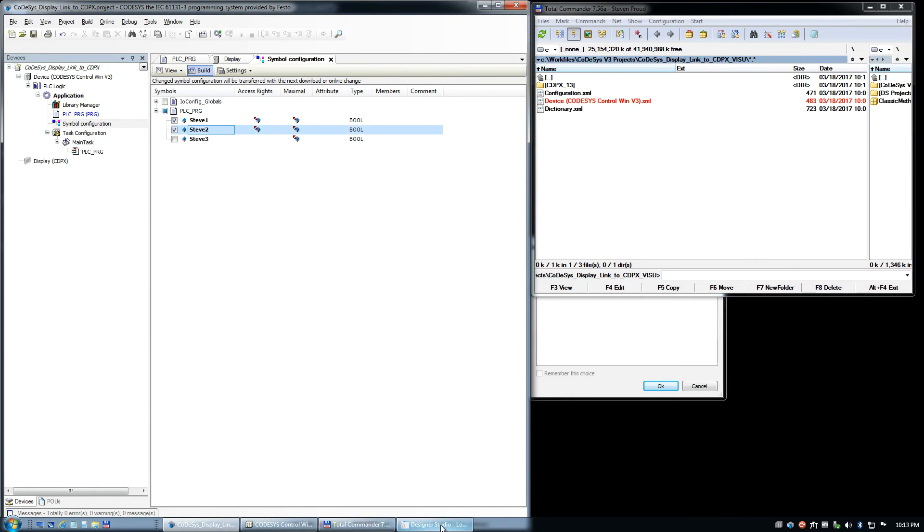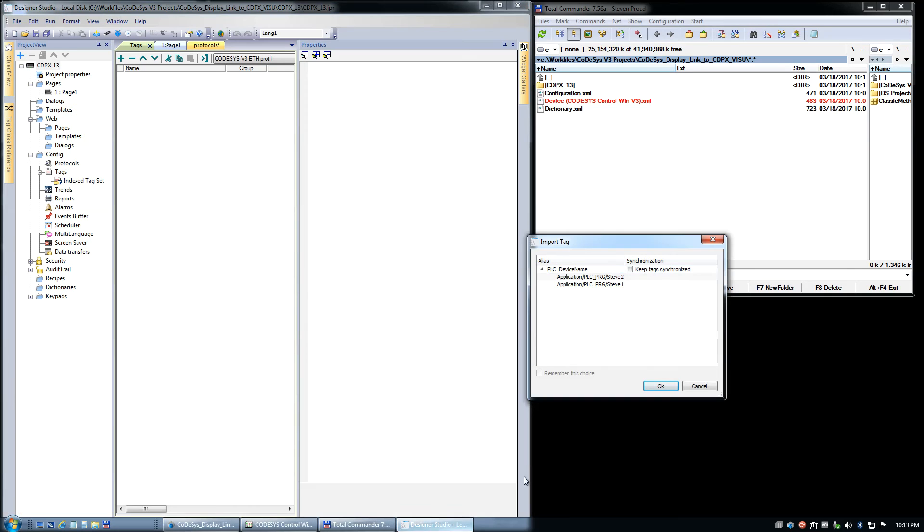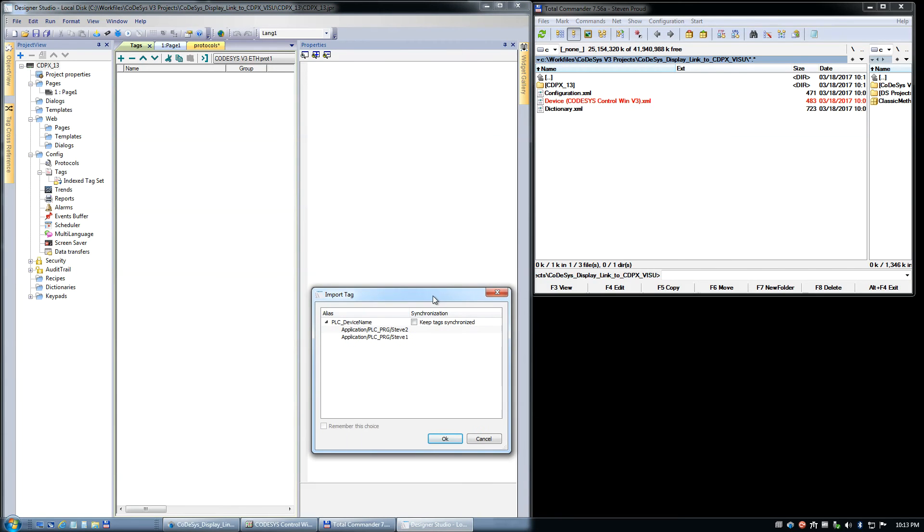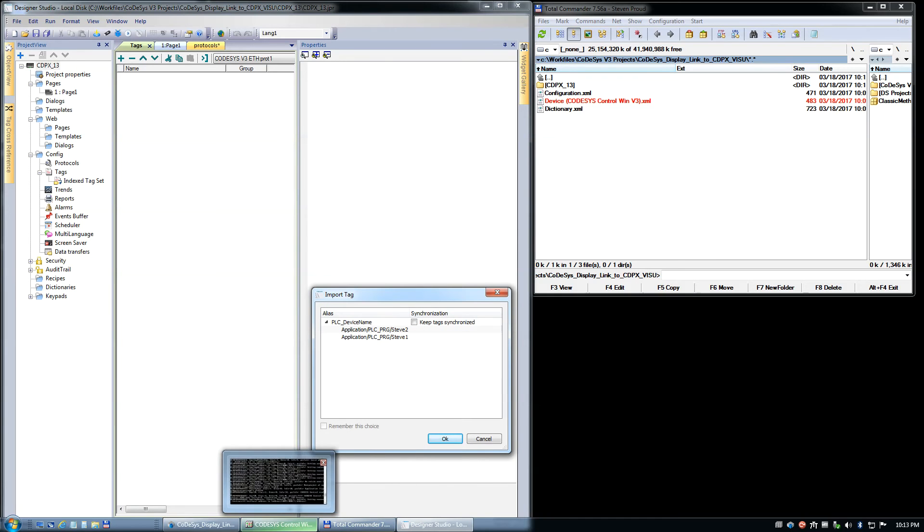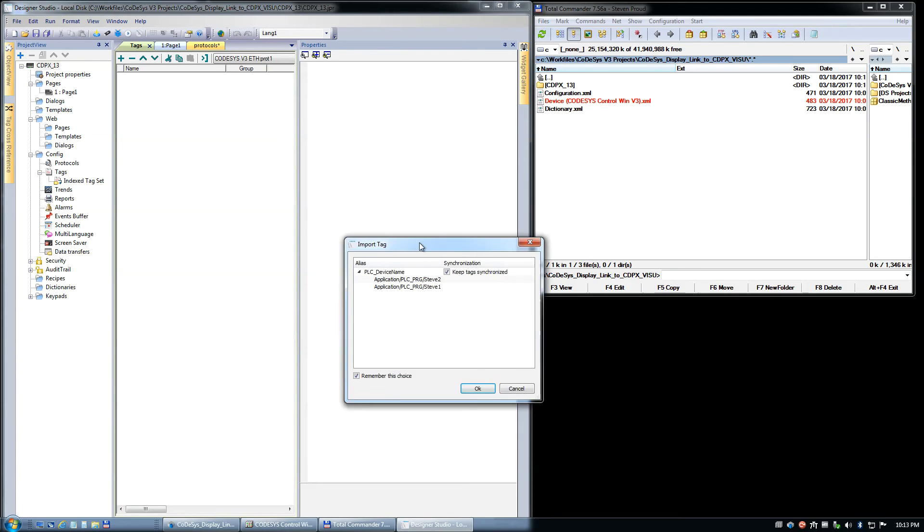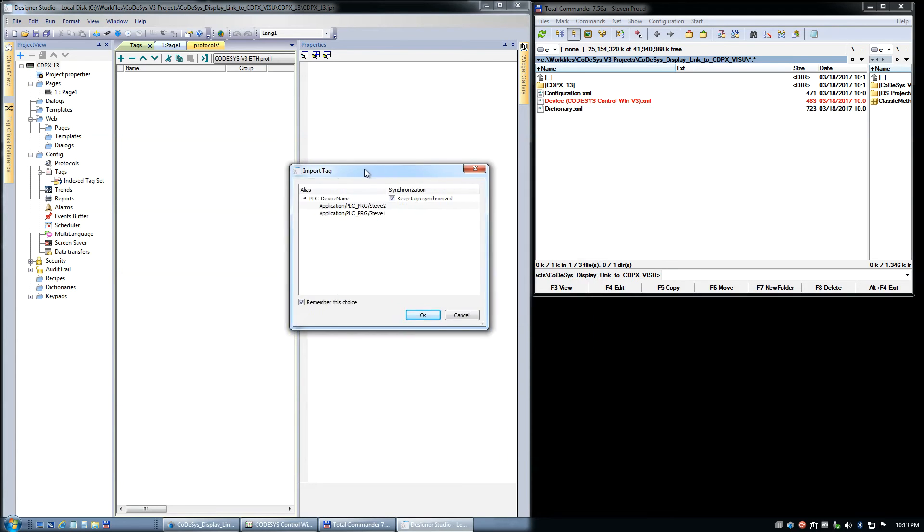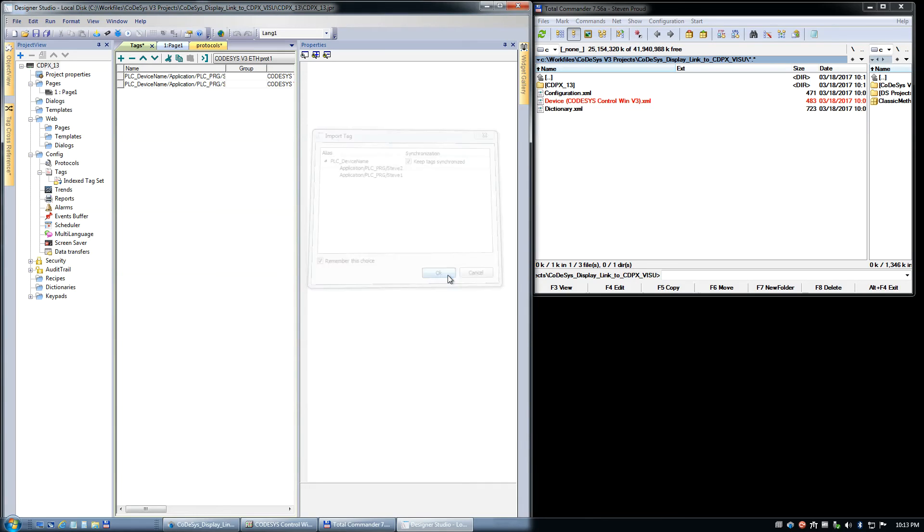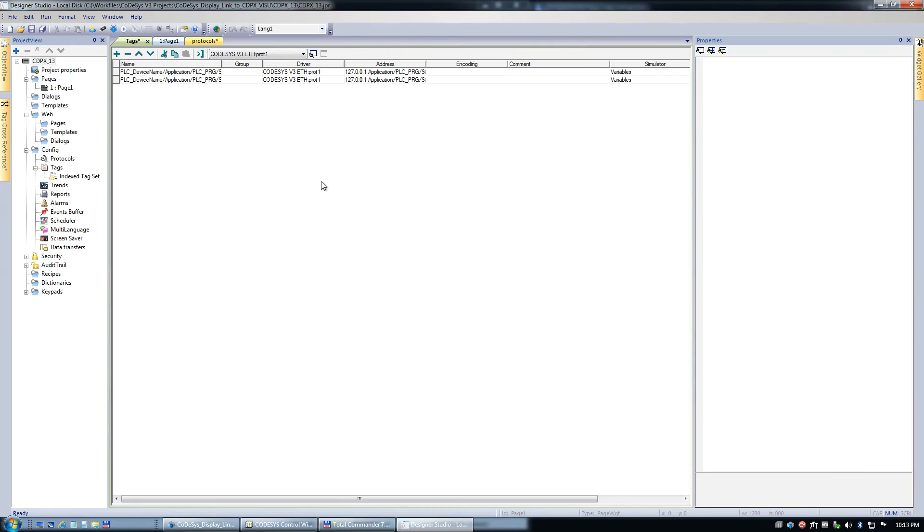Now we have a pop-up, and immediately I get this little puppy come up. This is important. Keep tags synchronized and remember this choice. That is key. Don't ever not click that, or you will run into problems. So I hit the OK button. Now, lo and behold, in my HMI project, without doing anything, without finding and importing the tags, it's already done this now.